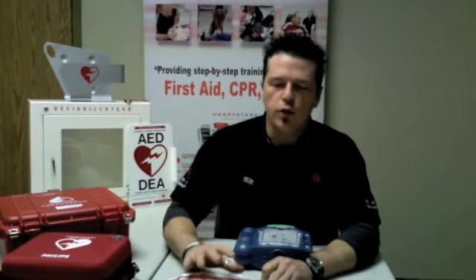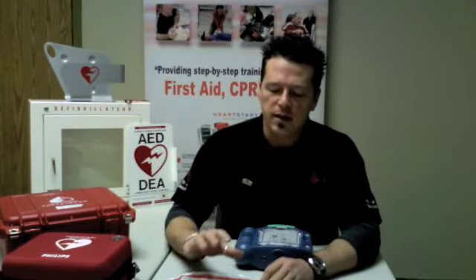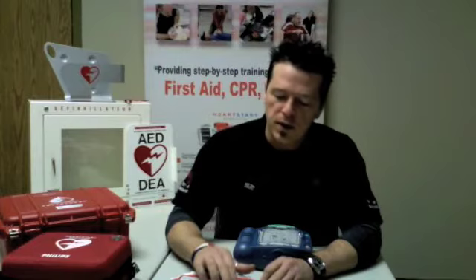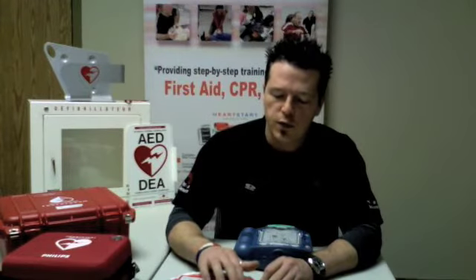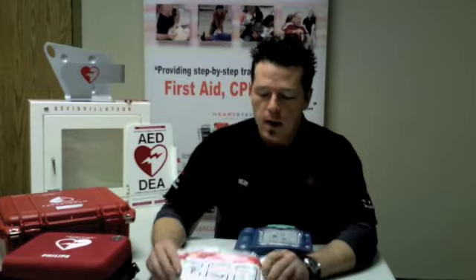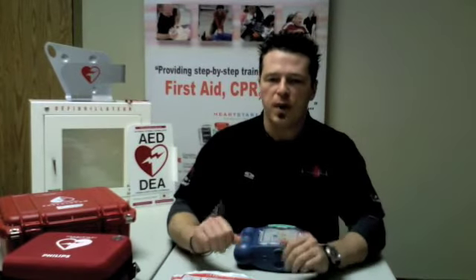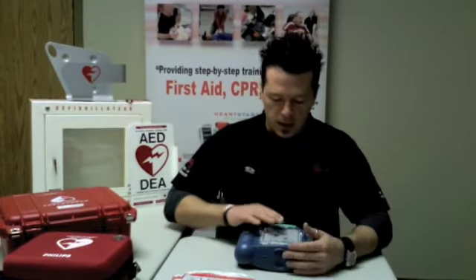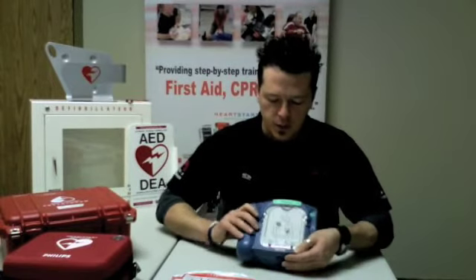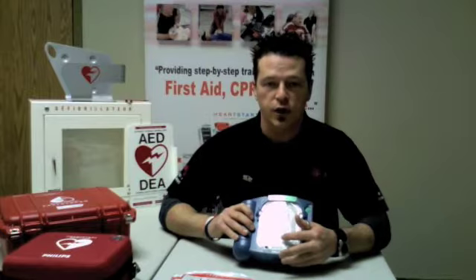Before going any further, a couple things need to be known. The electrode pads have an expiry date from the date of manufacture, which means that in this case, the expiry date on these pads is 12/2008. Basically, that means that this set of pads is actually expired and cannot be put in the machine. Now, there is a 2-year expiry date, usually. In the defibrillator itself here, it's 03, so March 2011. So that means that it is still good.